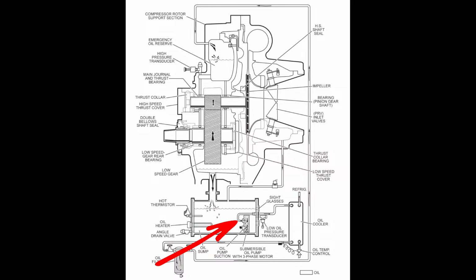One of the things, okay, so moving beyond the heater and the temp sensor itself, our oil level, like the volume of oil, will have an impact. The lower volume will cause higher temperatures because that oil is moving through the system faster and getting less processing time. Because the flow rate of the oil is increased due to lower volumes, it's not spending as much time in the sump, just kind of naturally cooling. That will have an impact. Even if it is going through the oil cooler, it will compensate. It does adjust, and I'll talk about that in a second. But we want to make sure we have enough level. And if you're down into the minimums, especially at a high load like you mentioned, that will increase your operating oil temperatures as a whole.